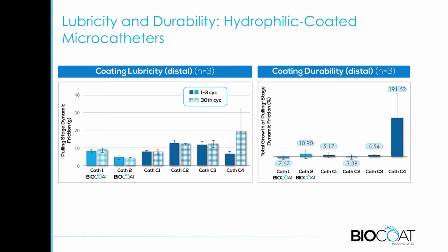Let's look at the lubricity and durability first. You can see that most of these catheters have similar lubricity results, around 15 grams to a little less than 10. All of these were evaluated on that pad test, where we apply 470 grams and pull, so it's a dramatic reduction in the friction. One of the catheters had durability that was not quite as good, but most of them were pretty good in terms of durability as well as lubricity. And this is how most people evaluated coatings up to 7 to 10 years ago: lubricity and durability. But when you look at the particulate piece, it changes the interpretation of these coatings.